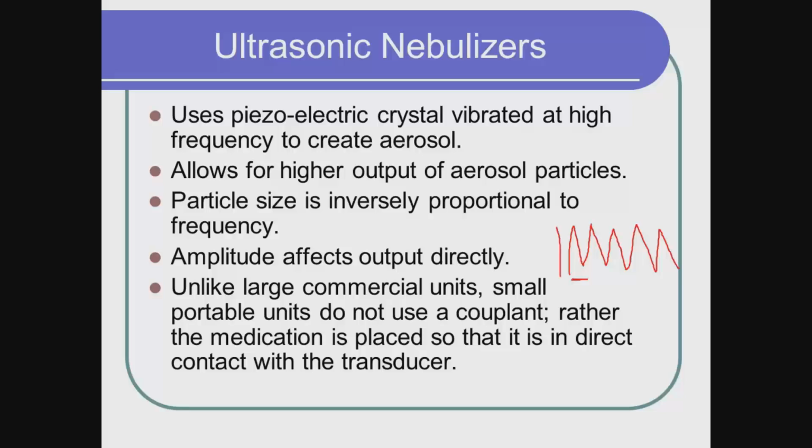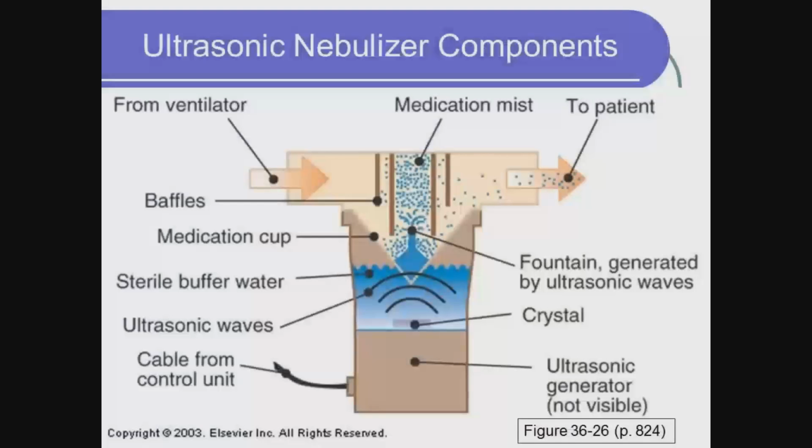What we end up having is really the medication placed into what's called a couplant. It's a little cup that sits above the ultrasonic nebulizer. So here's my crystal that's vibrating. My medication is in this little medication cup. These ultrasonic waves that are created bombard against the medication cup, which then creates the nebulization. So it's kind of a backwards way of doing it.